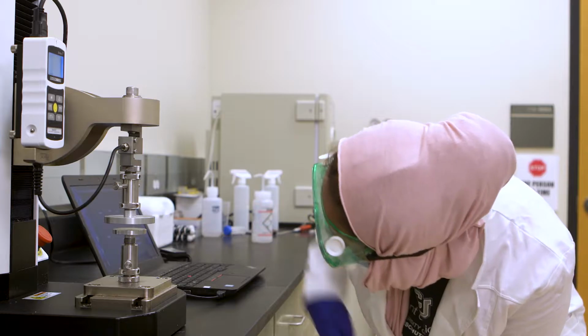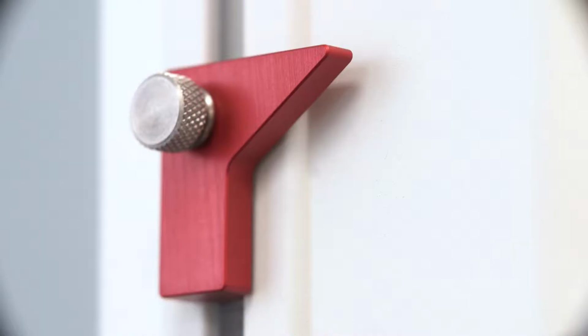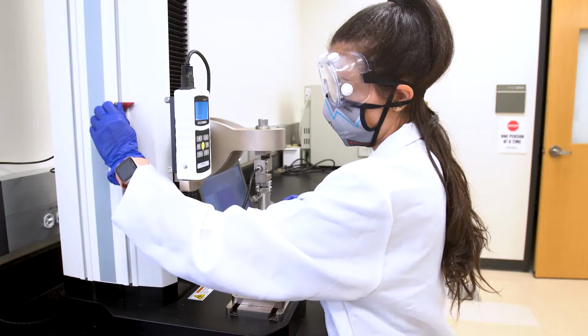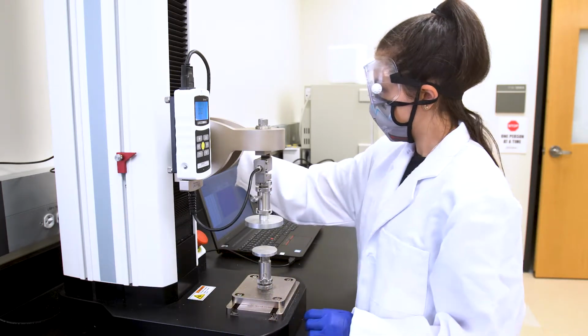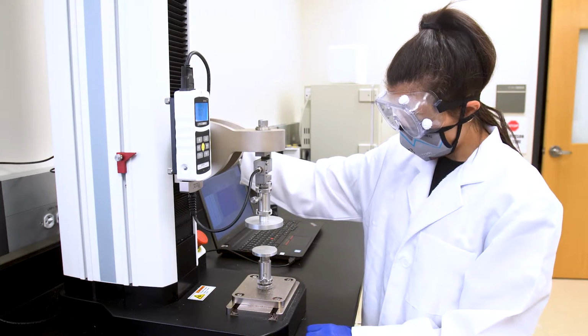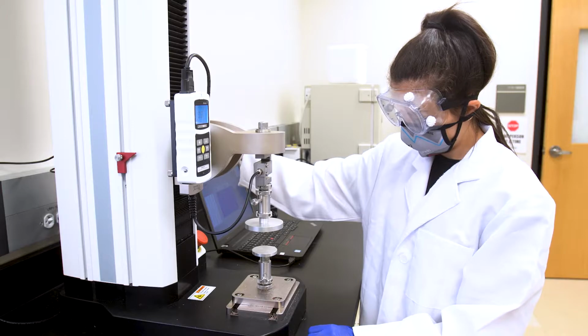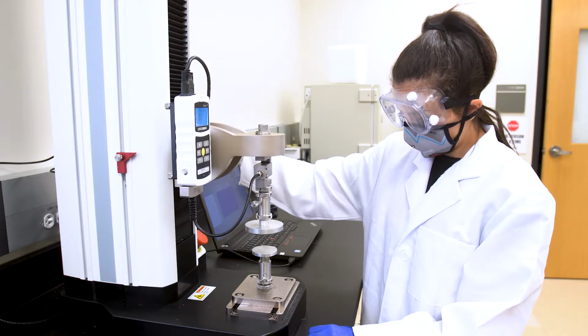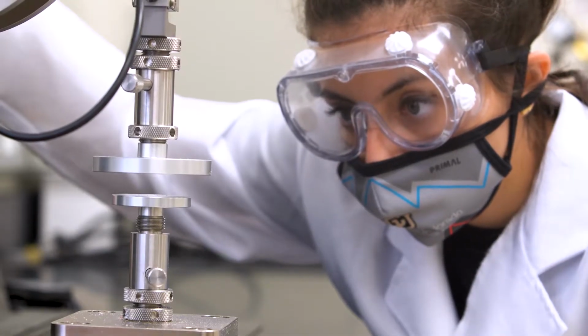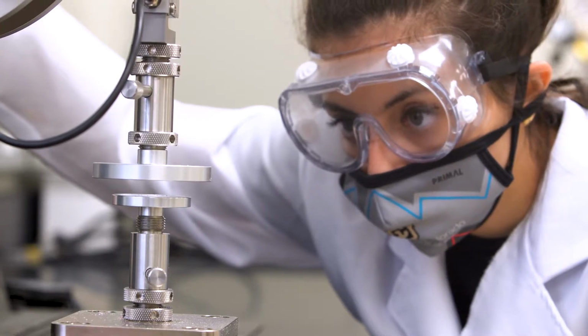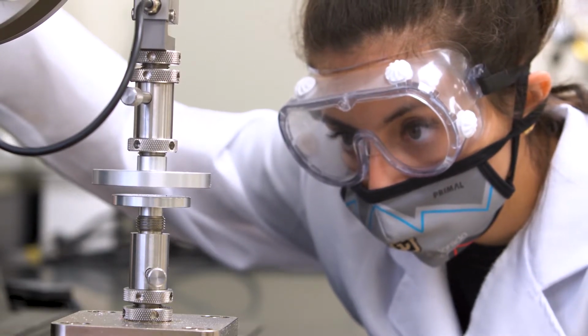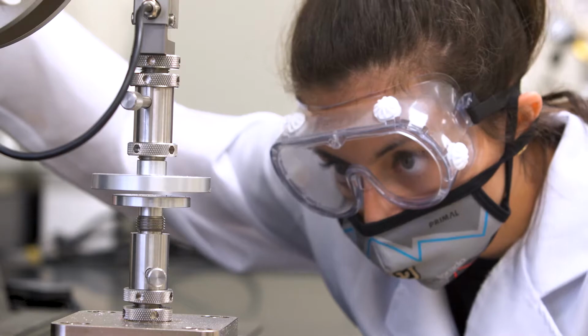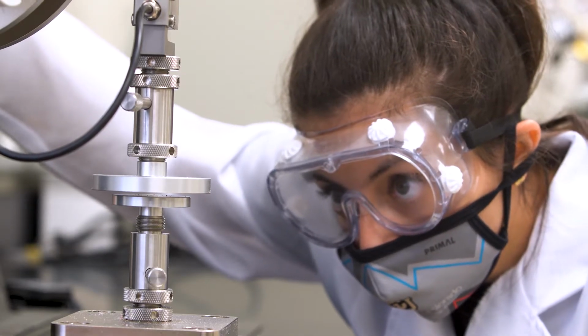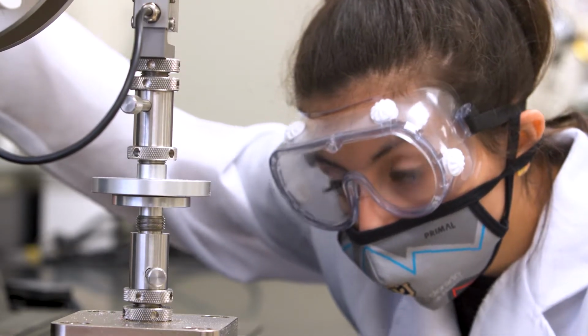To set the stop limits on the load frame, follow these steps. Loosen the thumb screw on the lower grip stop marker and lower it to the bottom position. Ensure the speed is set slow enough that you can get the grips very close without them running into each other. Drive the top grip until it is nearly in contact with the bottom grip. Be prepared to stop the grip to prevent running the grips into one another. You want around 1 to 2 millimeters between the two grips if you are testing the sample to failure.